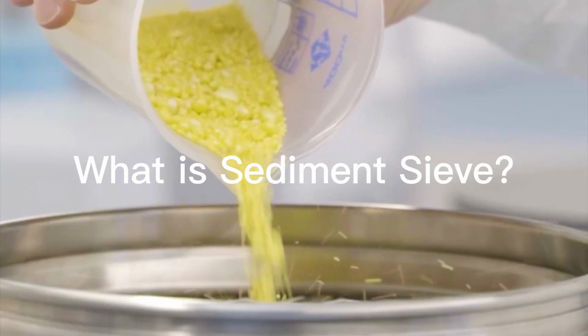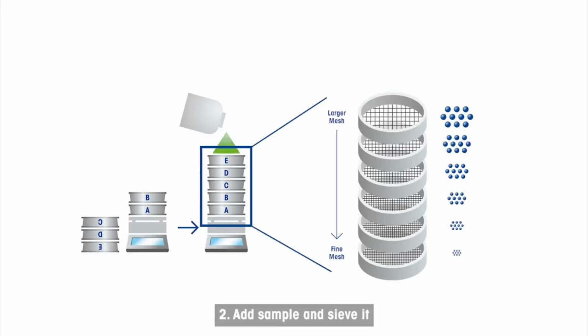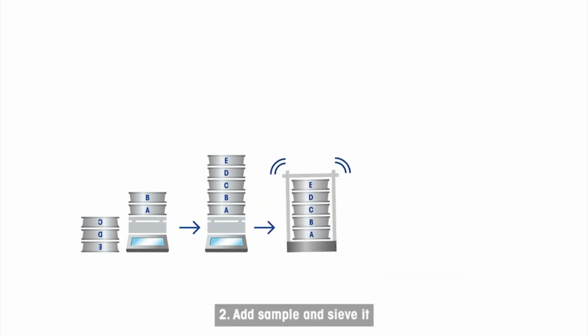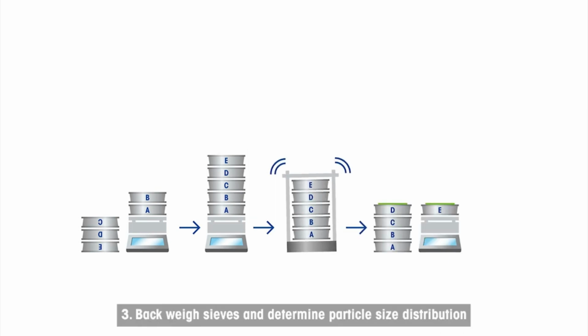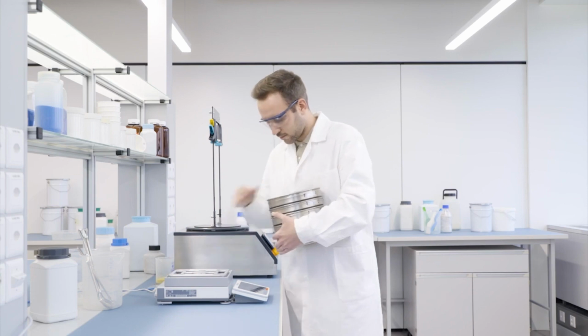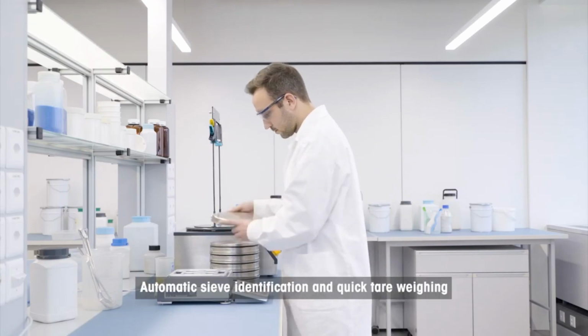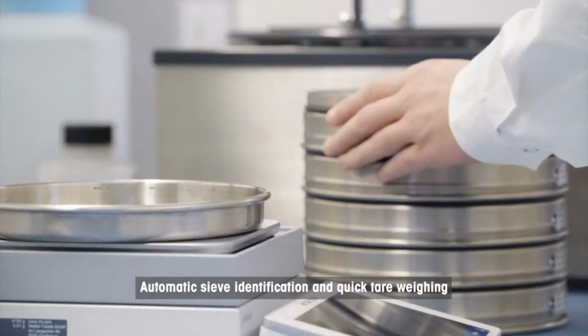Sediment sieve. The sediment sieve is used to determine the particle size within the sample. It has many mesh sizes to separate different sediments by filtering out the material. The sediment sieves we see in the laboratory have 1 mm and 500 micrometer sizes. This equipment can be used on non-organic or organic grain material, including sand, crushed rock, clay, grain, and seed, depending on the method used. The result of particle sizing from this equipment helps to identify the sediment layer.